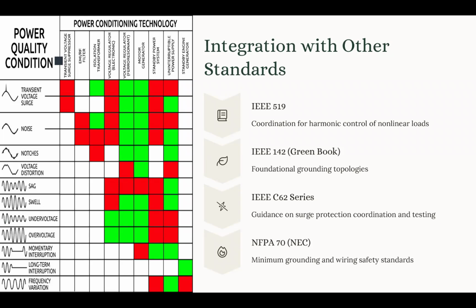One would be IEEE 519, which is harmonic control for power systems. This standard specifies maximum harmonic voltage and current distortion limits to prevent overheating, transformer derating, and waveform distortion. Now, we have IEEE 142, which is known as the Green Book, which covers the grounding of industrial and commercial power systems, and the purpose of that standard is to provide fundamental grounding topologies for industrial and commercial systems. Now, another complementary standard is IEEE C62, which is a family of standards covering surge protection. This standard provides guidelines for surge protective devices and their design, selection, and coordination.